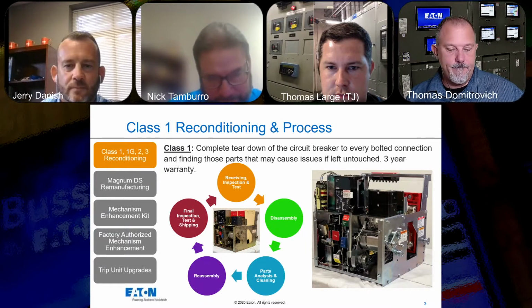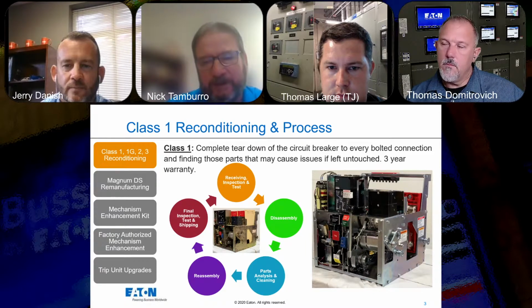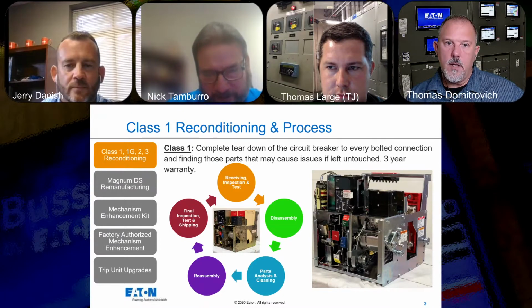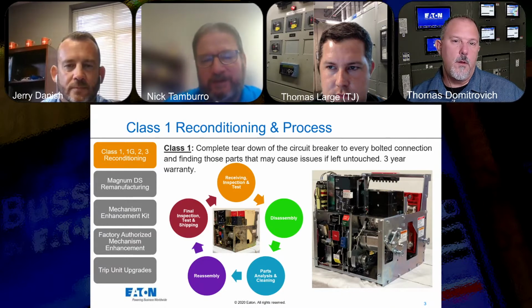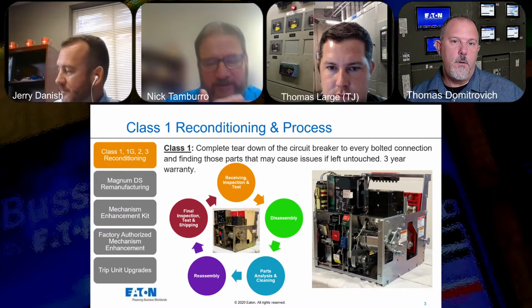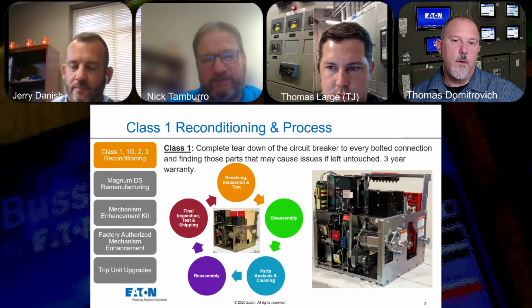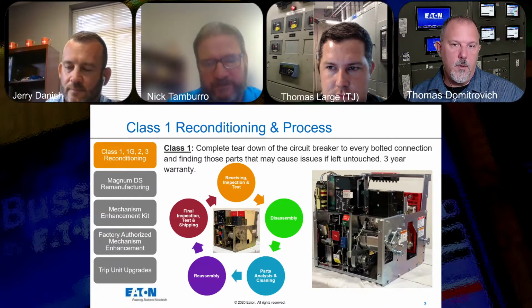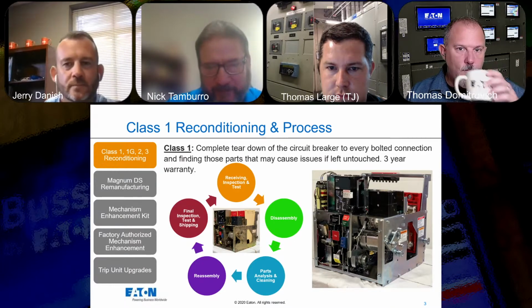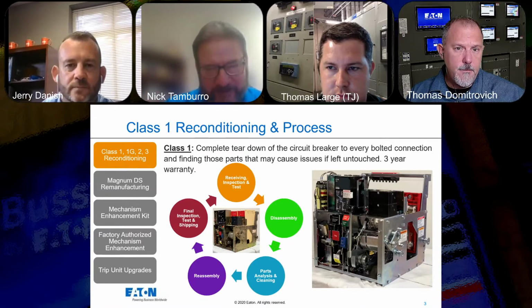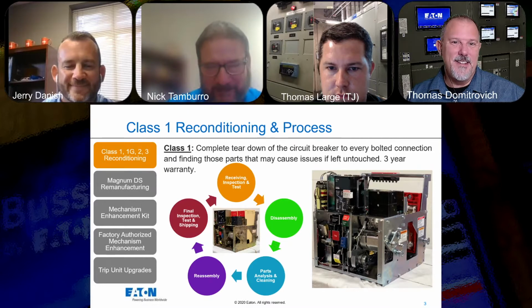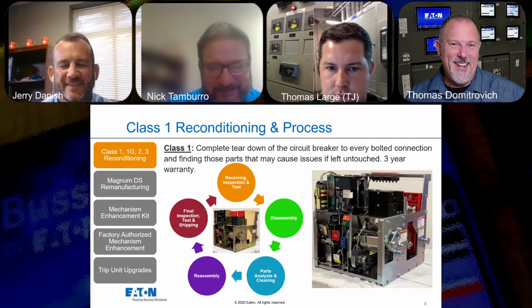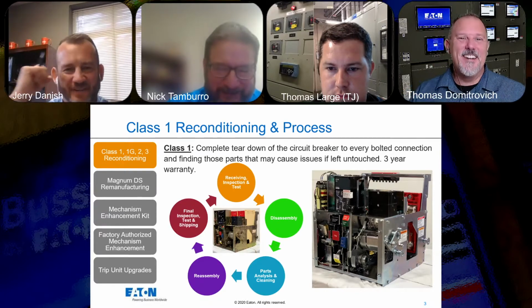But we would test it based off the rating plug. If you have a 1600 rating plug, all your test values would be based off that 1600 amps. So you get 120% of long delay pickup, and then short time, so it could be anywhere. We typically try to duplicate customer settings. If it came in and they upgraded the trip system, we try to duplicate what the old one was set at if we can. Now, if they have instantaneous set at 10 times and it's a 4,000 amp breaker, after we recondition it, we're not going to put 40,000 amps in it because it defeats the purpose of the reconditioning. But we will set it up to go at that level. Okay, I gotcha.